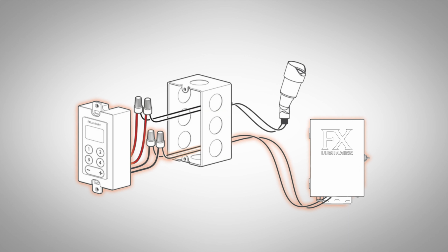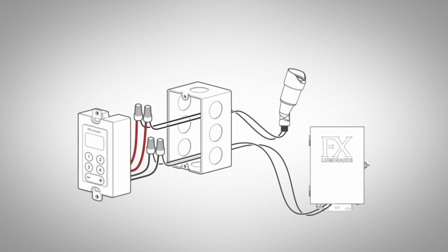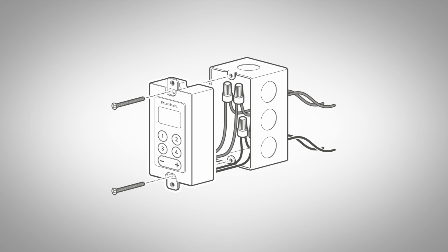Connect the black wires to the field wires that are connected to the transformer, labeled 12V in. Connect the red wires to the fixtures that will be controlled by the dimmer, labeled 12V out. Secure the dimmer into the junction box using the supplied screws.